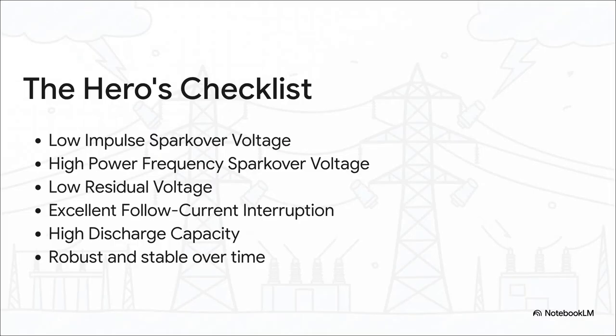So, if we put it all together, you get this kind of hero's checklist. A top-tier arrestor has to react to surges in a flash, but completely ignore normal voltage. It keeps that residual voltage super low. It's a master at cutting off follow current. And it's got to be tough enough to take multiple hits over many, many years without breaking down.